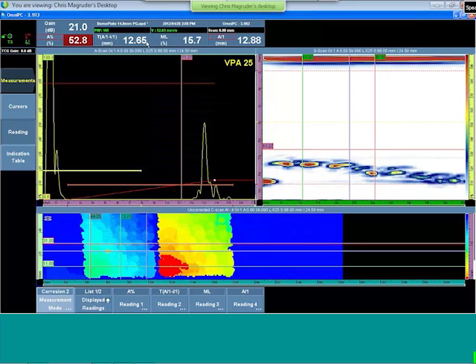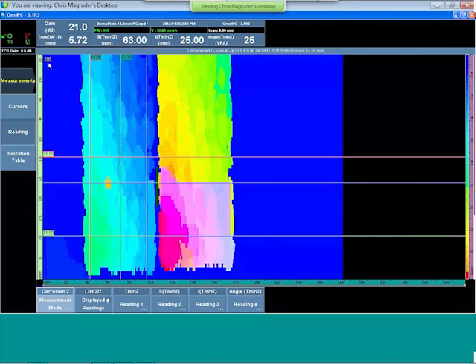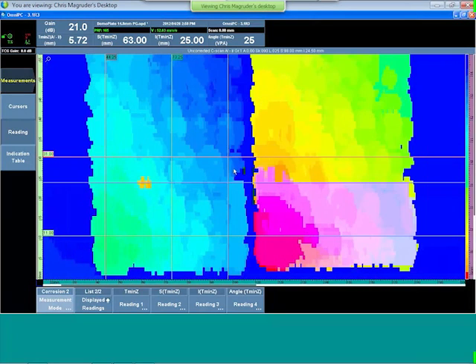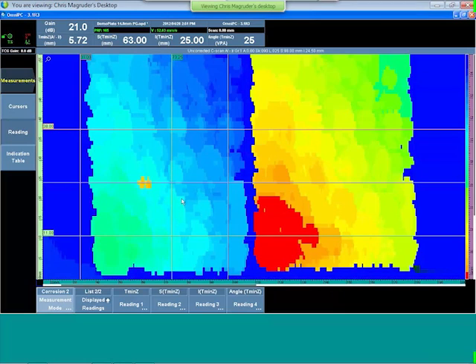So using these readings, we also have a series of readings that have a Z in them, and that means zone. So if I create a zone with my cursors, and on the offline analysis version of this, there are some tools built in, keyboard shortcut functions, keystroke shortcuts that allow us to overcome not having the touch screen on our computer, but using the same software as the instrument. So I'm going to create a box with the reference and measure cursors, this red cursor here and this green cursor.